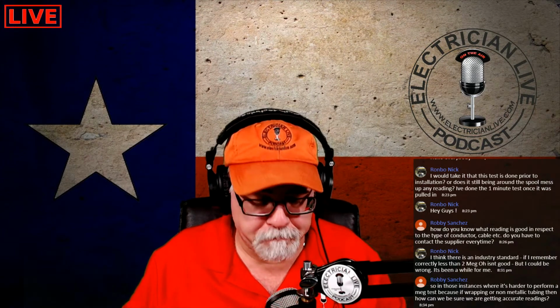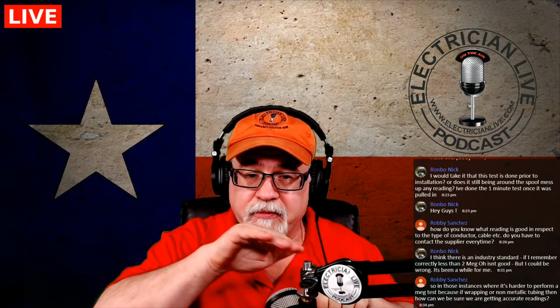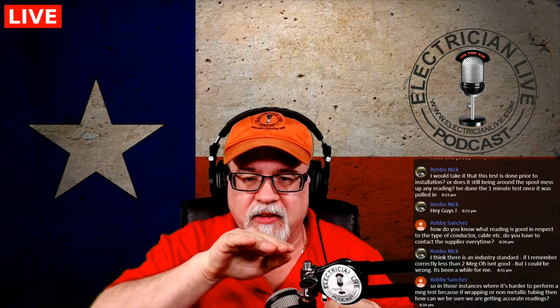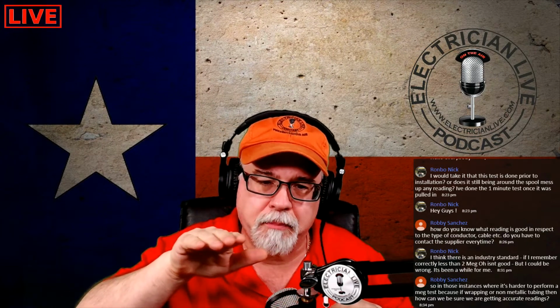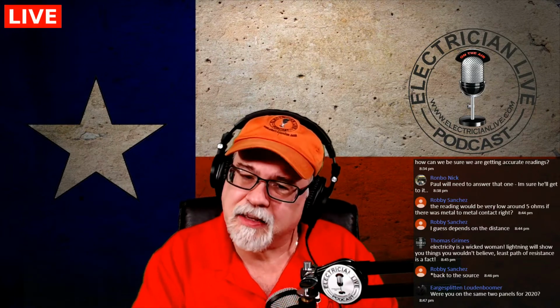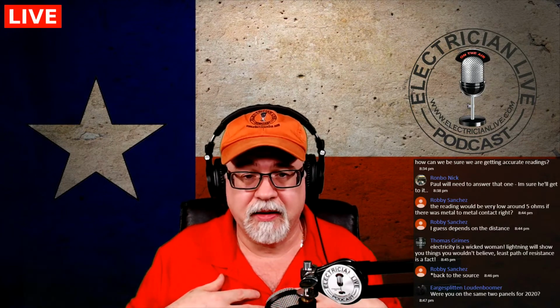Now, with that said, if I do the time resistance, all I'm looking for is to make sure that when I'm taking it at 30 seconds, and I get to the 60 seconds, at that point up to the 10 minutes, it does not drop below the value that we got at 60 seconds. Okay, so it continues its climb up. Okay, as far as meg reading values, I typically tell people that, look, anything that's 20 to 25 megaohms and greater, I'm happy with. Okay, NETA doesn't say that, but that's what a wire and cable manufacturer is going to say because that is pretty high insulation values, and we're taking all the conditions into consideration with that.